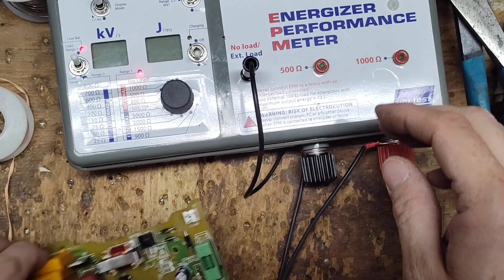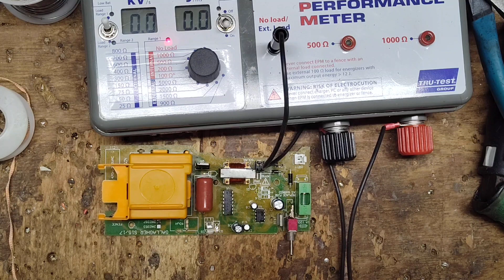Let's put our meter on here and see what we get. We're going to go across fence and ground, which is down here, and we're going to see what kind of power we get out of it. Voltage wise, it should be about 8 to 9,000 volts usually, typically. 9.2, 8.6, 9.6, 8.9 - so we're right in that 9,000 plus or minus voltage range, which is right where it should be.